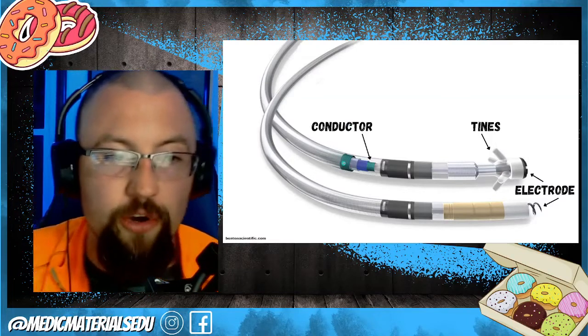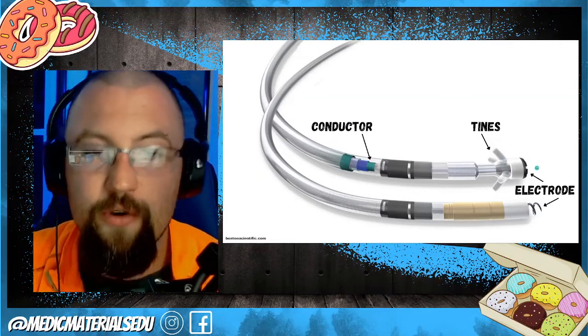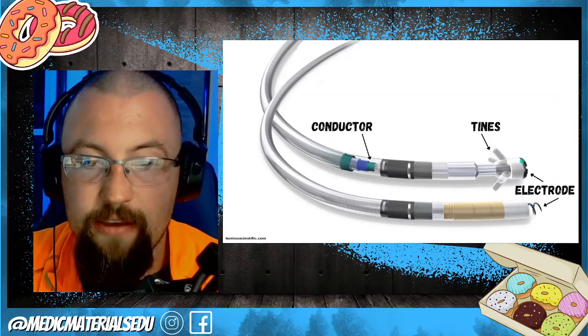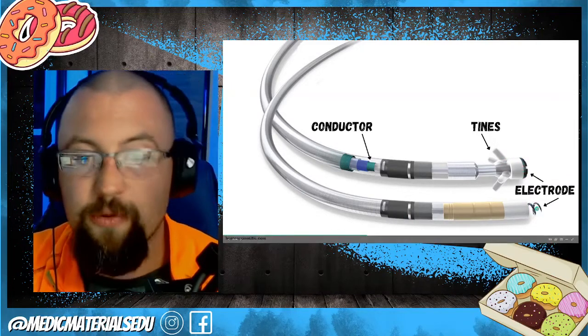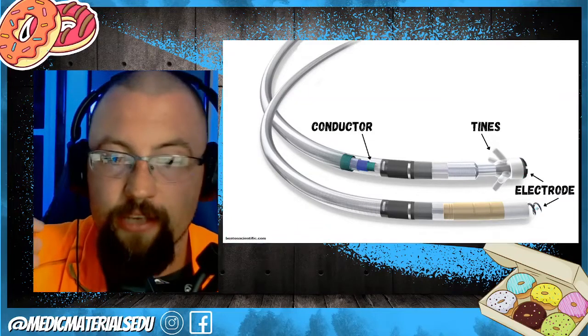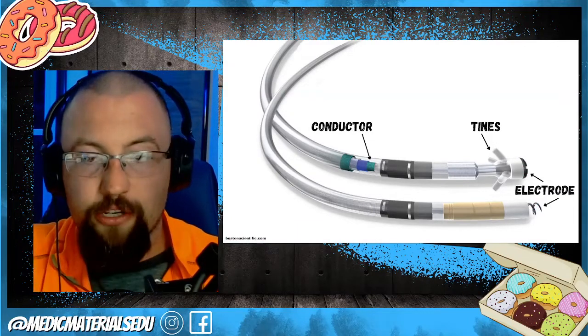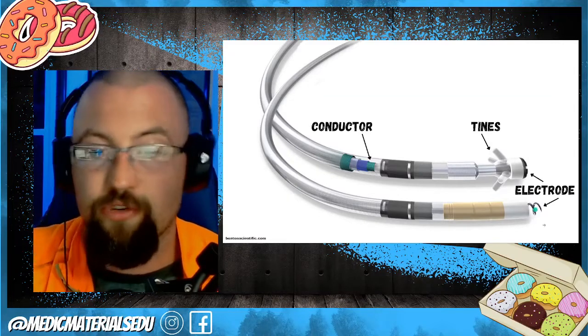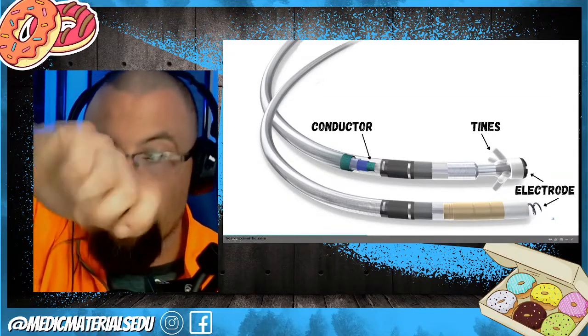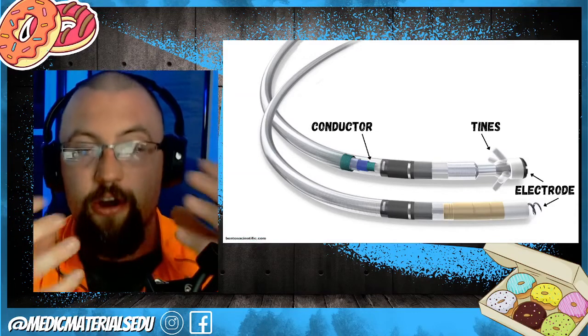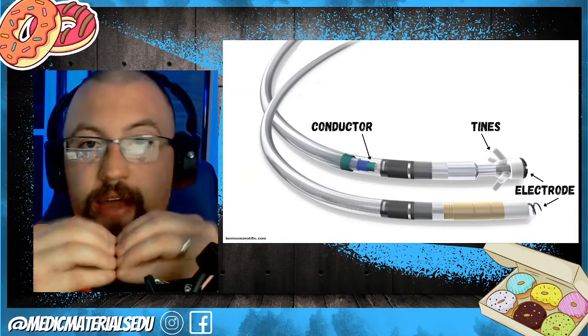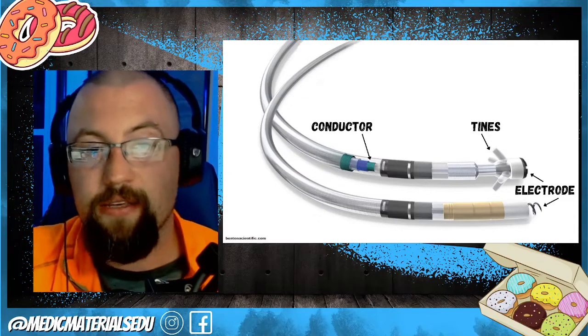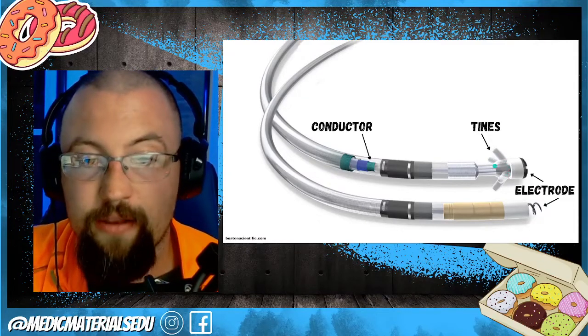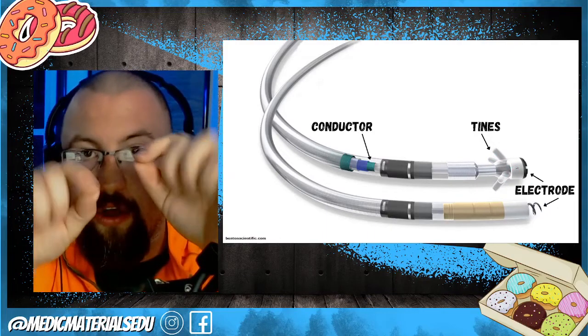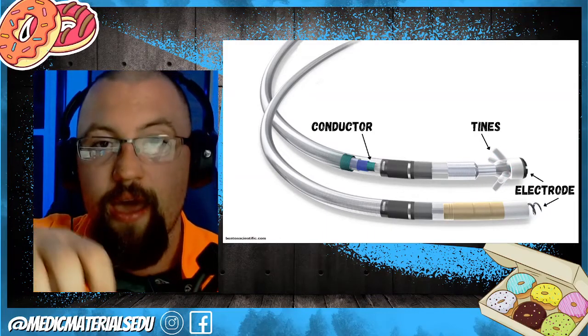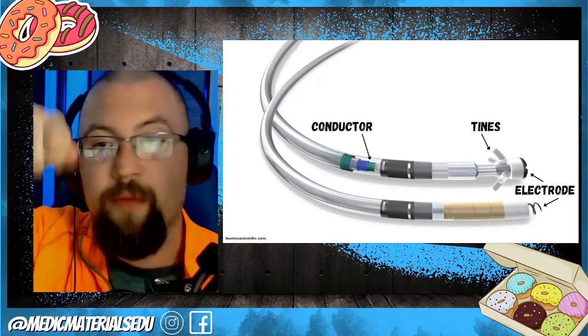So you have a coiled conductor, then you have the electrodes on the end. So this one is a flat electrode. This one is a screw electrode, and those actually touch the myocardium. So the screw electrode, they will actually screw it into the myocardium, and then the myocardium grows around it, scar tissue's in, and that's how it's held in there. Whereas with the tine one, this one on the top, they cut a little hole, they stick it in there like a fish hook, and then it grows around it, and you can't pull it out like a barbed fish hook.